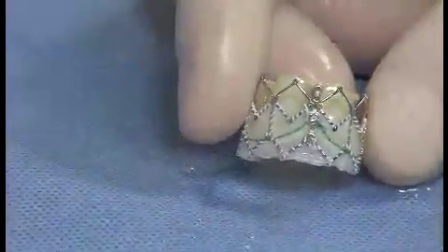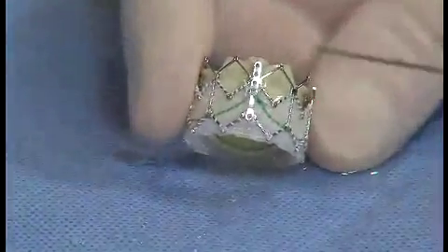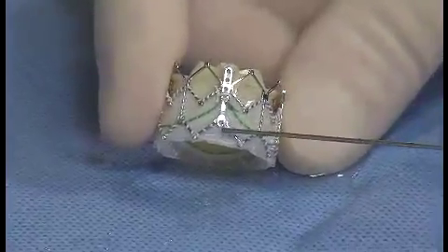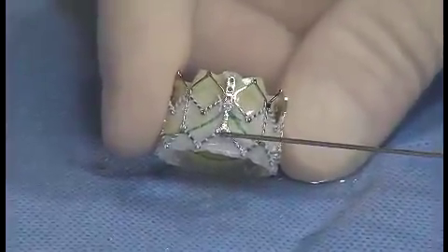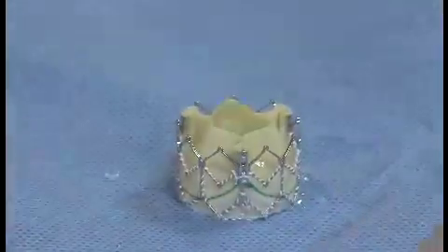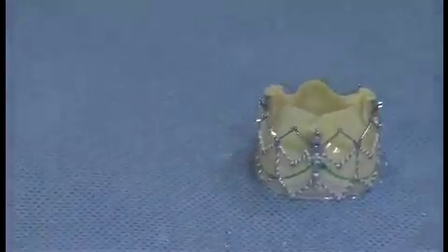So how to be sure that you mounted the valve in the correct position? You see here, there are some 3 distal metal points, and a single one here. This is going to be the right ventricular position of the valve. So it's obvious that we have to mount the valve in the correct spot, but of course it's very, very important. Okay, so Roberta, go ahead and we will show you the process of crimping the valve.